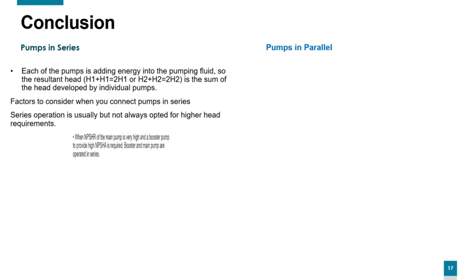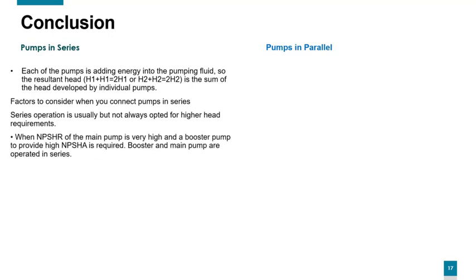Factors to be considered when we connect pumps in series. Series operation is usually, but not always, opted for higher head requirements. That means when the NPSHR of the main pump is very high, a booster pump with high NPSH available is required. Booster and main pump are operated in series.